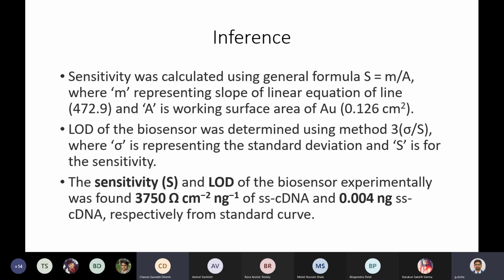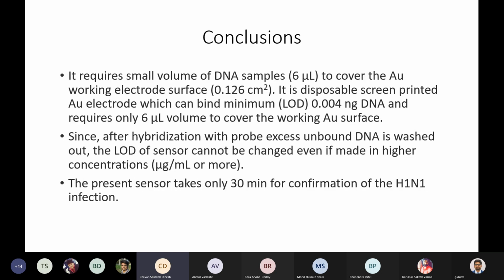The sensitivity and limit of detection of the biosensor were found to be 3,750 ohm centimeter square per nanogram of single strand cDNA, and 0.004 nanogram respectively. From this, we can conclude that it requires a small volume of DNA sample, 6 microliter, to cover the AU working electrode surface, which is 0.126 centimeter square. It is a disposable screen printed AU electrode, which can bind a minimum of 0.004 nanogram DNA, and it requires only 6 microliter volume to cover the working electrode.